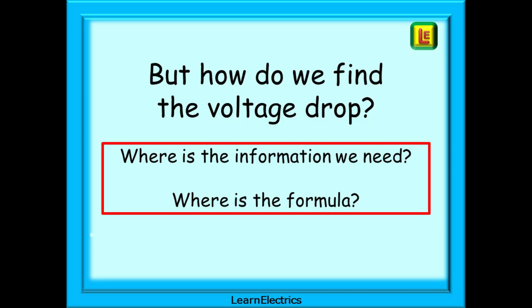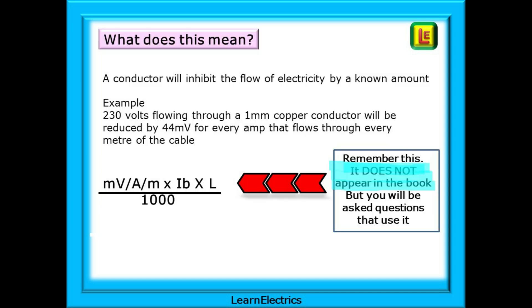But how do we find the voltage drop? Where is the information that we need? And where is the formula? For that, go back one page to the beginning of section 6 on page 429. There's some good information here and we want to look at the third paragraph. We're told that for a given run of cable we can calculate the voltage drop in millivolts by multiplying the voltage drop given in the tables by the length of the circuit and by the design current or IB. What does this mean?